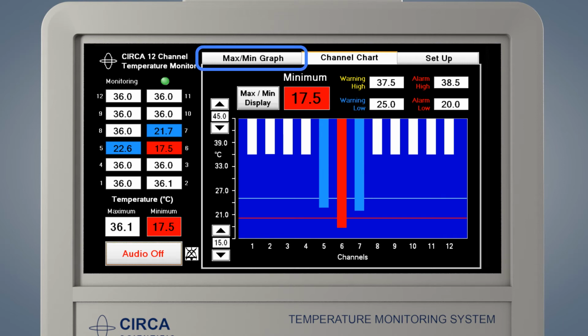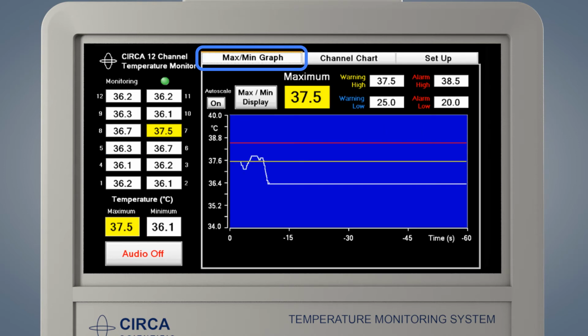By pressing the Max-Min Graph tab, the temperature data may be displayed in a different format. The Max-Min Graph display displays only the highest, maximum, or the lowest, minimum temperature. The temperature is graphed over the last 60 seconds. This display indicates the temperature and the rate of change. The alarm settings are indicated in the same manner as the channel chart screen. Likewise, the alarm functions operate in the same manner as the channel chart screen.